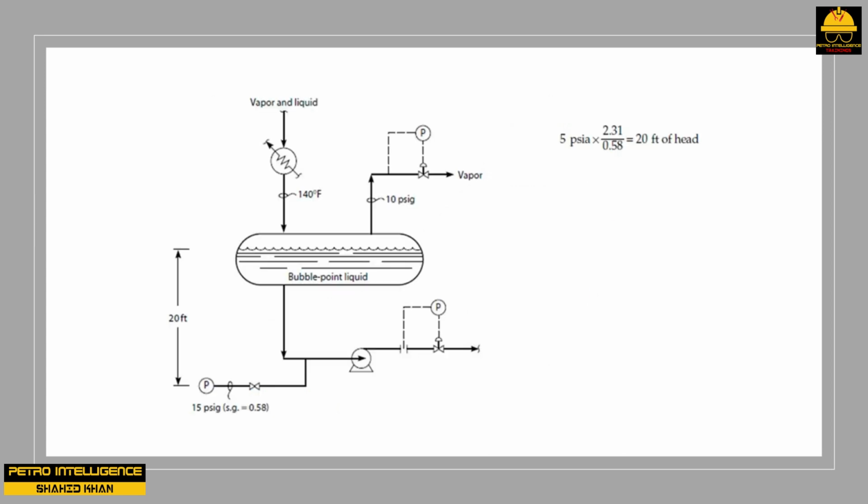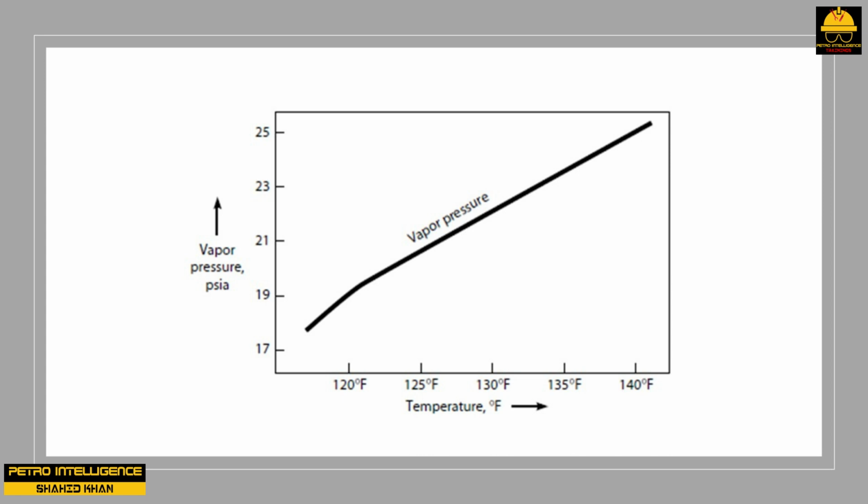Let's now assume that we wish to pump 300 GPM, not 250 GPM. If we open the flow control valve shown in the picture, the flow will momentarily increase. But within a few seconds, the flow will become erratically low as the pump begins to cavitate.